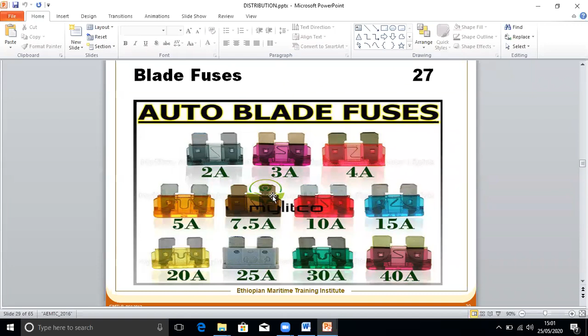Now, what is the normal operating current of a circuit? How do you decide what the fuse should be? For example, if the normal steady state current is calculated to be 10 amps, then your fuse should be 10 amps multiplied by 135%. That means 13.5 amps. So if the normal steady state current is calculated to be 10 amps, then a 15 amps fuse rating should be selected. 10 amps multiplied by 135% is 13.5. You will not get 13.5, that is why the standard size is 15 amps.